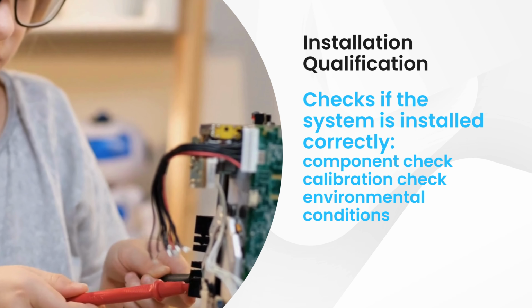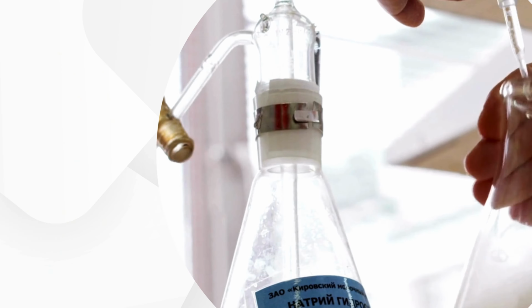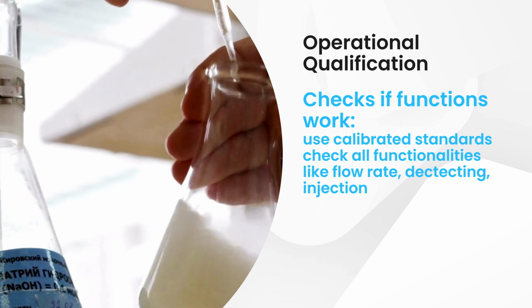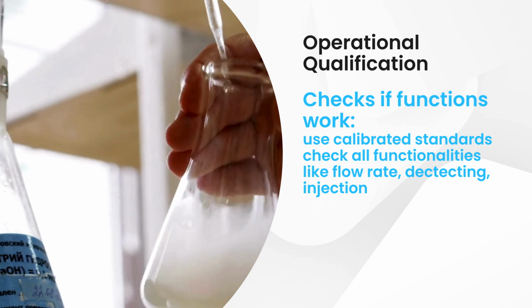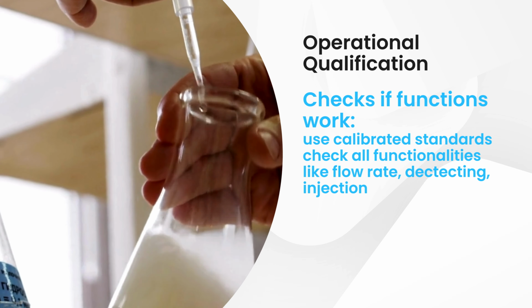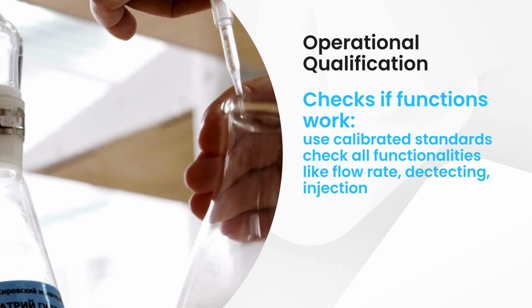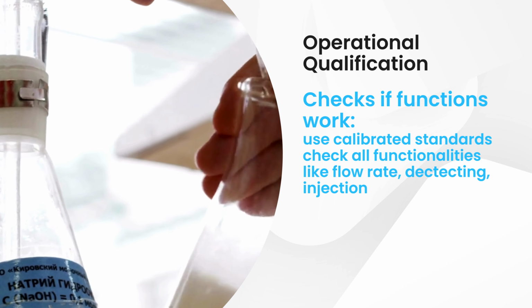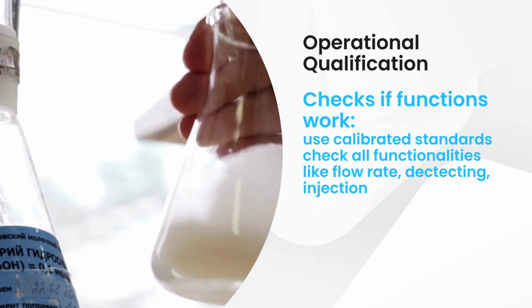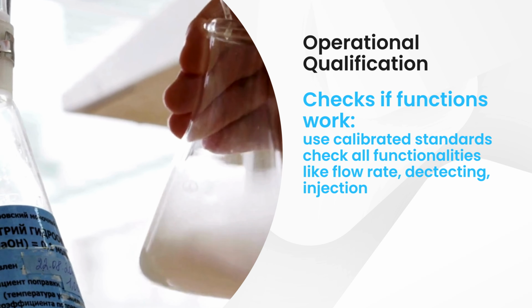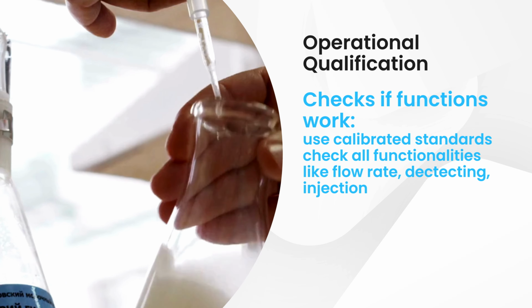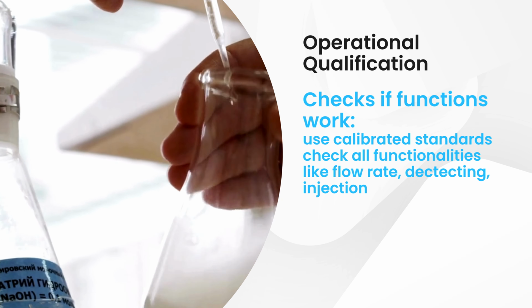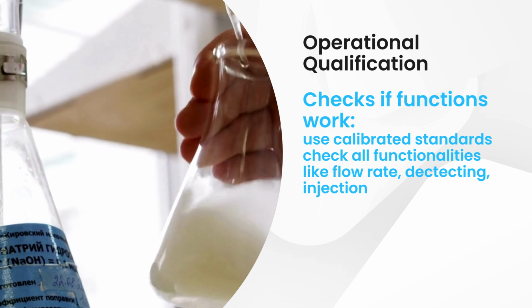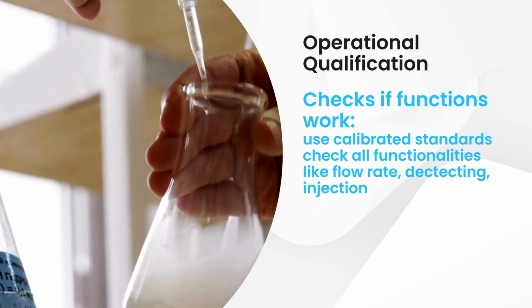Operational qualification. OQ is where you put the HPLC through its paces. You'll use calibrated standards and test procedures to verify performance. Examples include pump flow rate. Is it delivering the mobile phase at the set rate? Detector accuracy. Is it accurately measuring the concentration of your compounds? Injection precision. Is the injector delivering the same volume each time? Column oven temperature. Is the temperature stable and accurate?